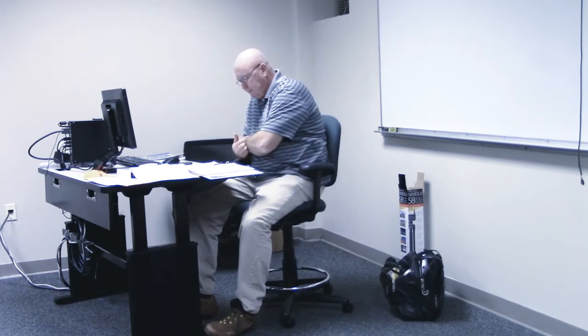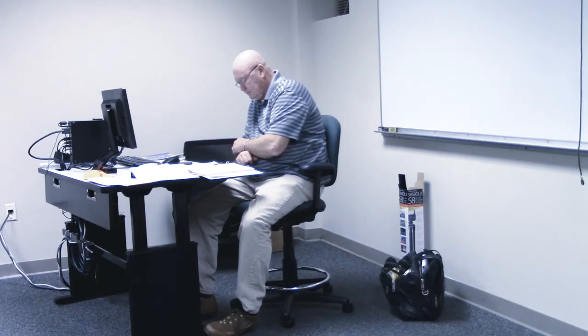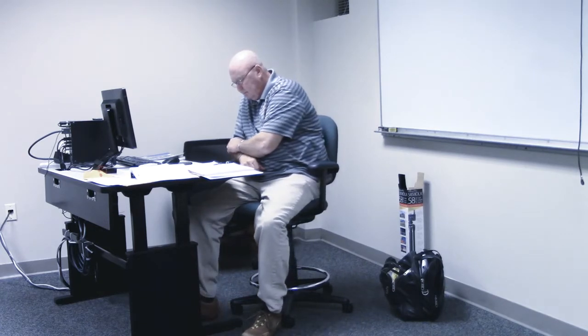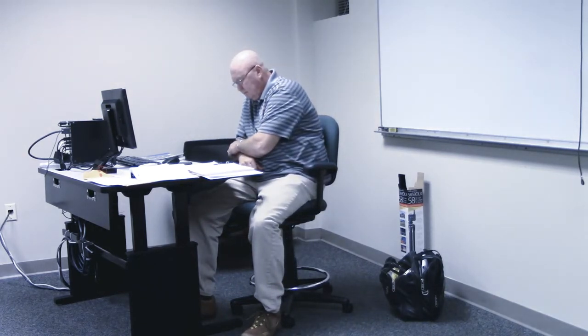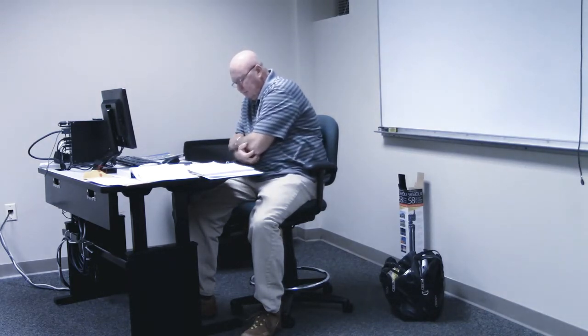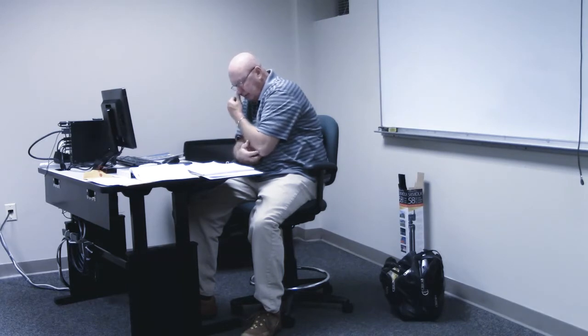Okay. Number 6. Per section 517.160(A), each isolated power circuit must be controlled by a switch or a circuit breaker having a disconnecting pole in each isolated circuit conductor to simultaneously disconnect all power. Okay, so we've got an isolated circuit. You may have multiple circuit conductors, and we have to make sure that they're all de-energized, don't we? So 517, we'll probably be looking at that in the code book in a little bit, but we're just going to fill in the blanks now.